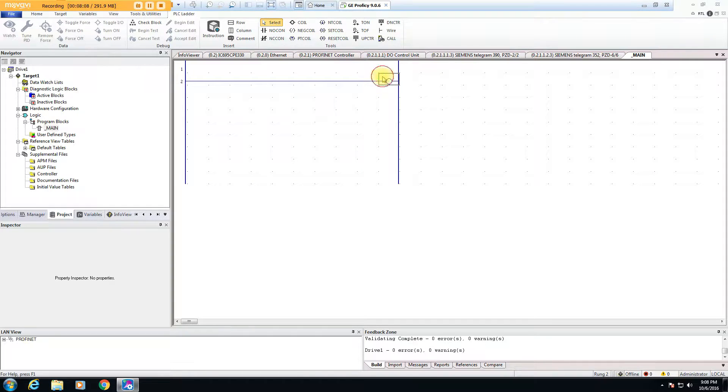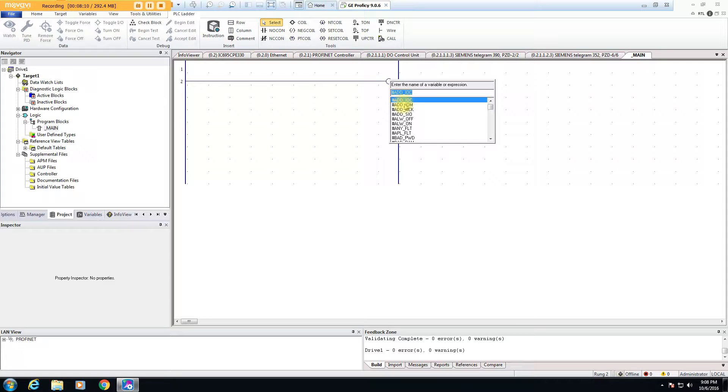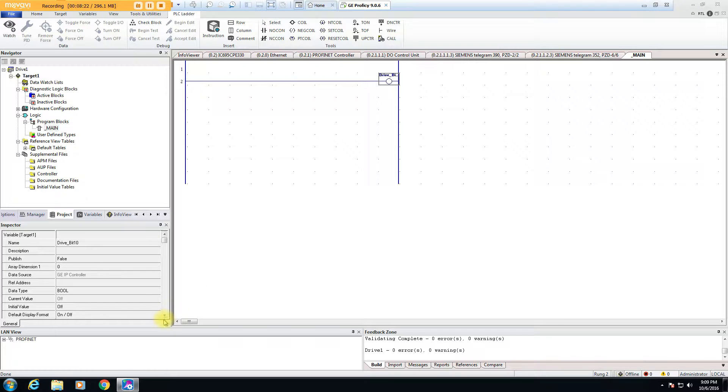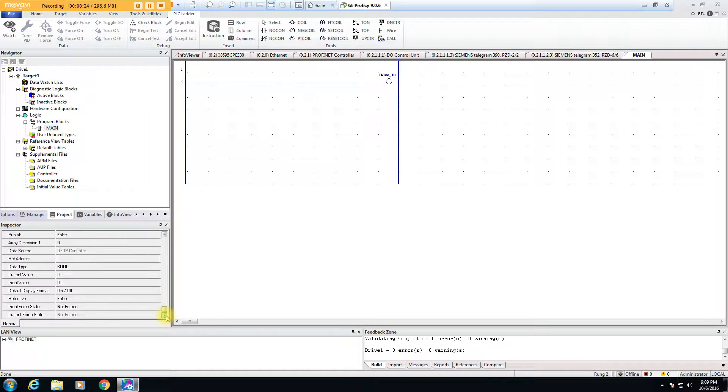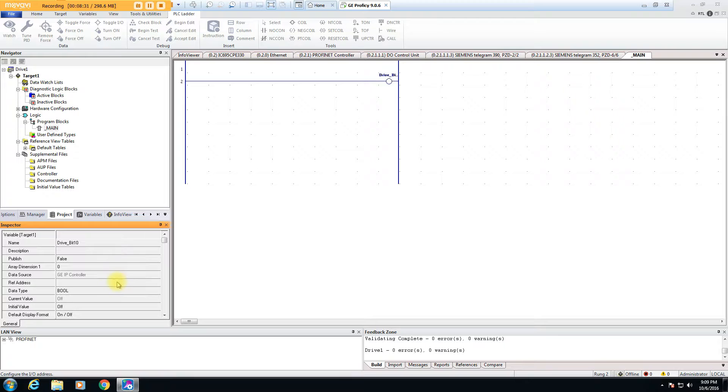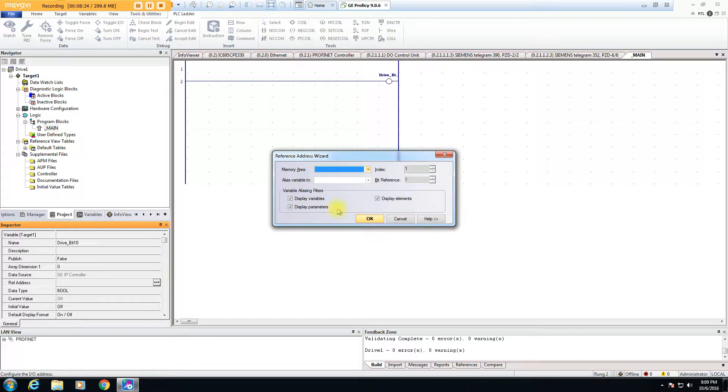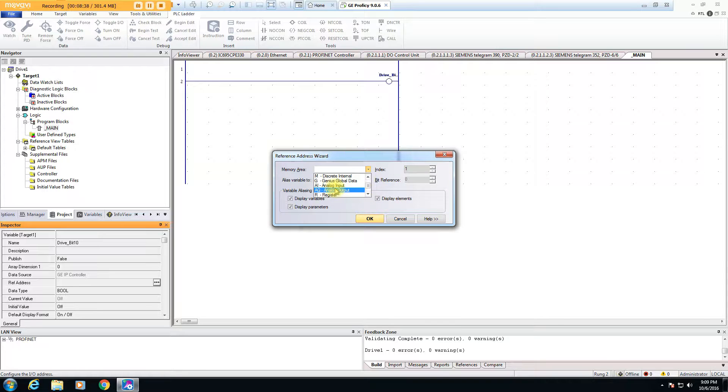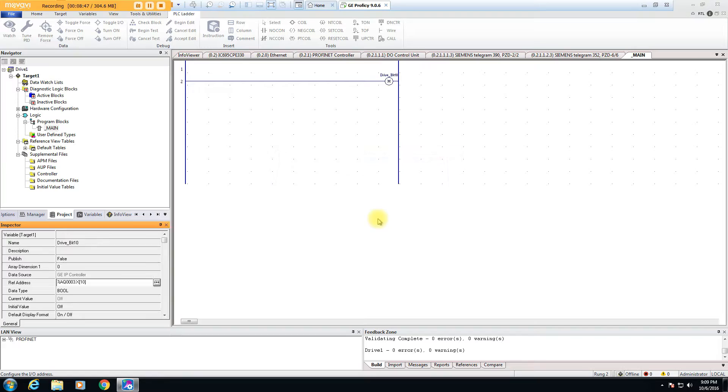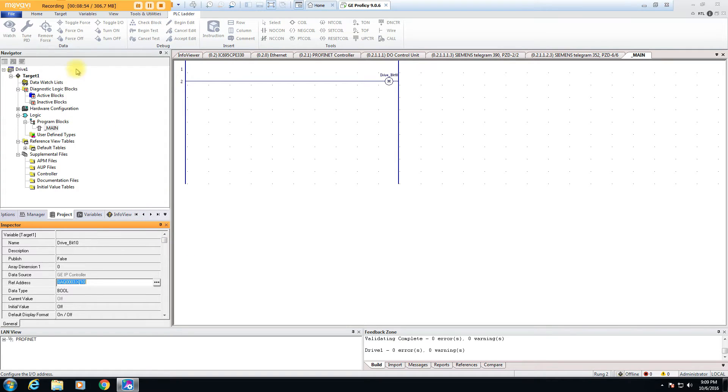The good thing here is that on PROFINET, the high byte low byte goes through the same order, so it shows up as high byte first in the drive. So bit 10 shows up as bit 10 in the drive. That's not the case with the Rockwell, because it's low byte first in the Rockwell processors and several others. So you gotta kind of know which way the bytes are gonna come through to make sure you're actually setting bit 10 in the drive itself. And if you look in the drive, you'll actually see bit 10 go high once you download the whole program including hardware.